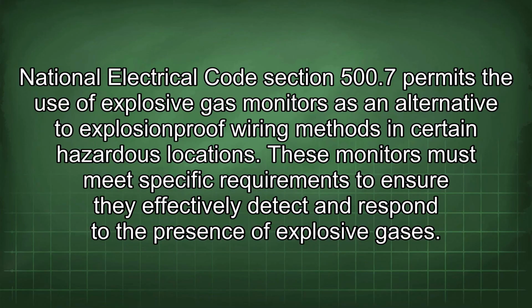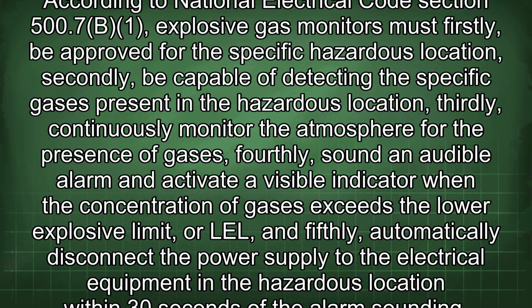National Electrical Code Section 500.7 permits the use of explosive gas monitors as an alternative to explosion-proof wiring methods in certain hazardous locations. These monitors must meet specific requirements to ensure they effectively detect and respond to the presence of explosive gases.